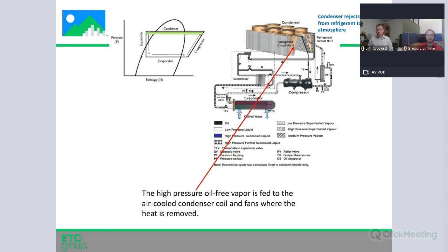And onto the condenser. So the condenser is on the high pressure side of the system. We're receiving hot pressurized vapor from the compressor. And in the condenser, we move from right to left on the diagram, and our refrigerant condenses. It goes from vapor down to a liquid. And in fact, in a condenser, we will generally have some degree of subcooling. In other words, after we've fully cooled it into a liquid, we'll continue blowing air across the condenser and continue cooling it.